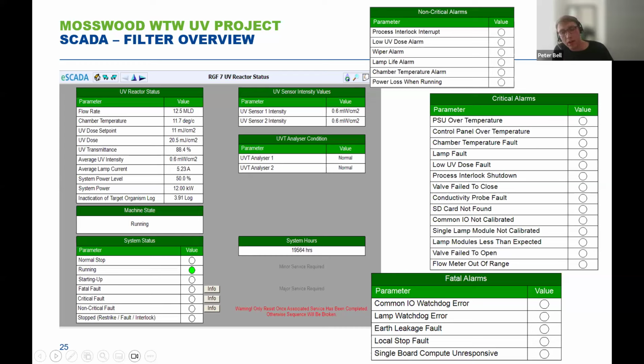And then on the right hand side, you can see some of the alarms that go with it. In total, there were around 30 alarms, not just the ones that you can see on the screen, but about 30 different critical alarms in there that we had to do end-to-end testing on. Obviously, we've done end-to-end testing on all of these, but the critical ones we made show in an easier fashion for the operators to see what the fault was, and gave a lot more information around that. So you can imagine this amount of data being replicated 12 times, an absolutely huge amount of data to process within our system, and build that into our alarm banks.